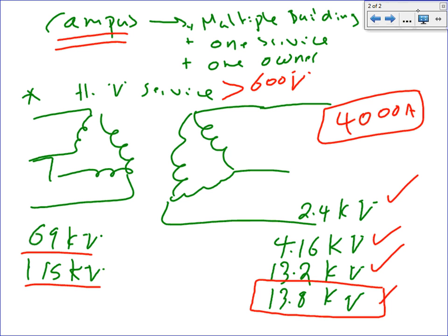When they reach building A, guys, the substation, here's your 13.8 feeder coming to the building. The high voltage section is here. They have a transformer to step it down to 480, because you can't put 13.8 across that light or across a chiller. You cannot. So you transform it down into 480-277, and from this side, now you get your 480-277. You feed all your mechanical equipment, lighting, and receptacles, then another transformer takes it to 120. So any questions, guys, about this?